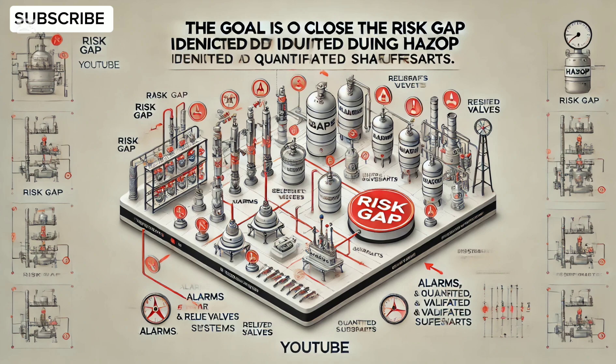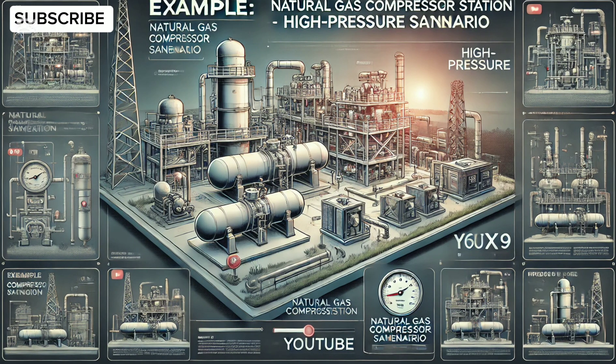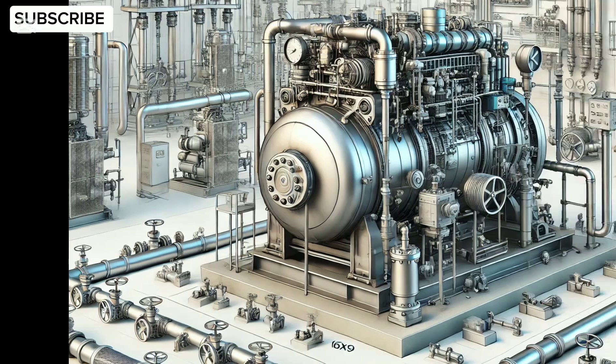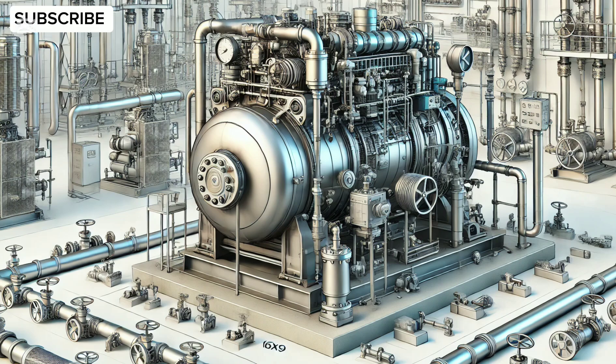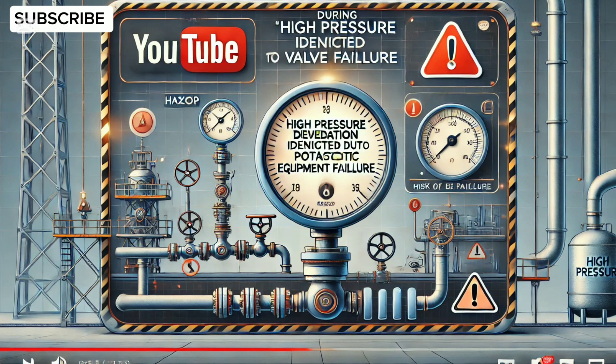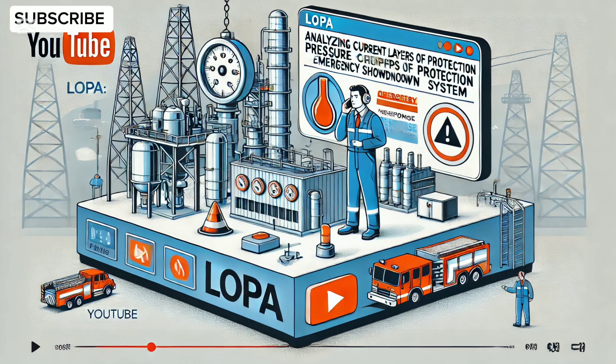Let's take an example of a natural gas compressor station with a high-pressure scenario. During HAZOP, a deviation of high pressure is identified due to potential valve failure, leading to catastrophic equipment failure. LOPA analyzes the current layers of protection: a pressure relief valve, operator response to high-pressure alarms, and an emergency shutdown system.